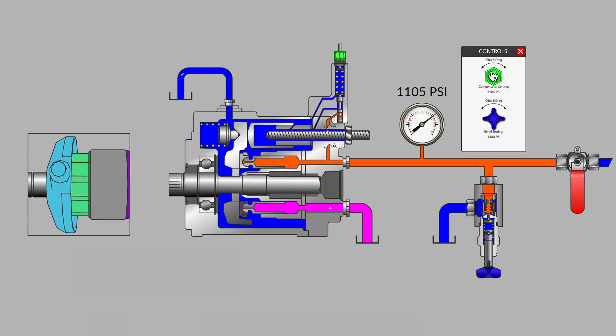It is fairly normal for the relief valve to be set at 300 psi higher than the pressure compensator on the pump.